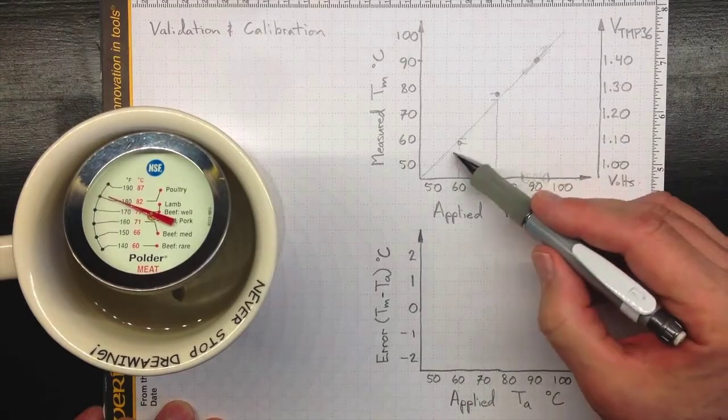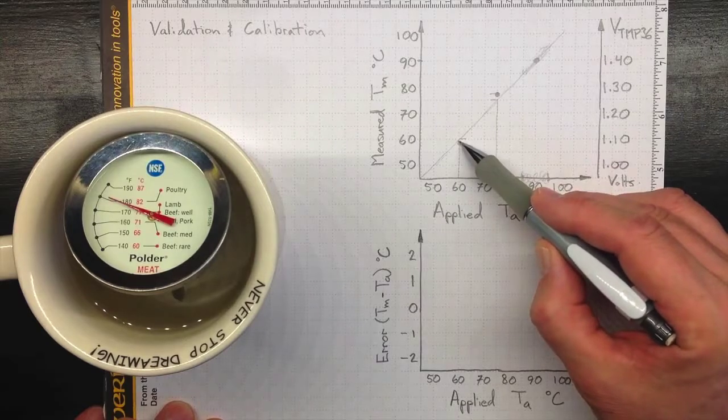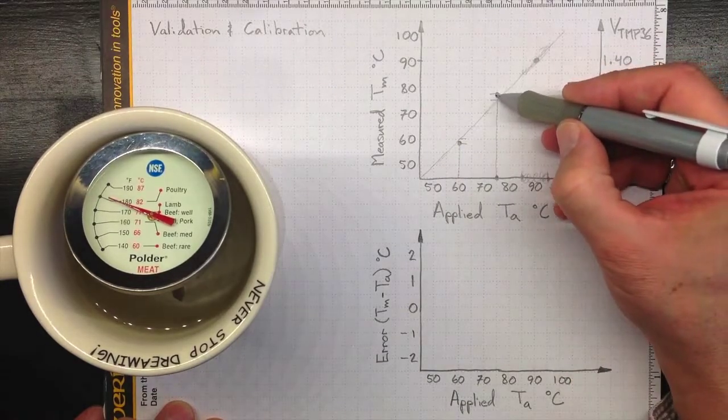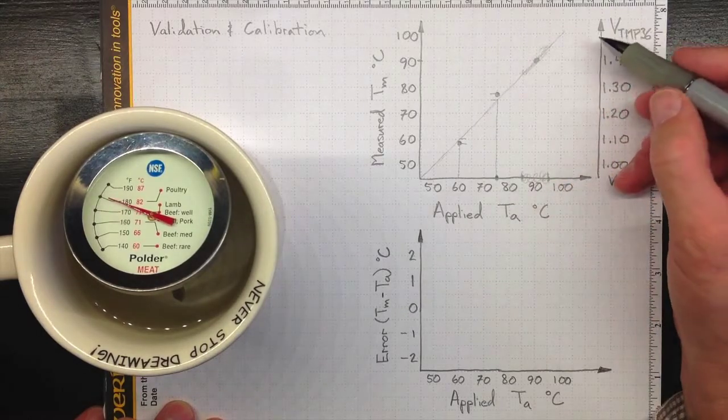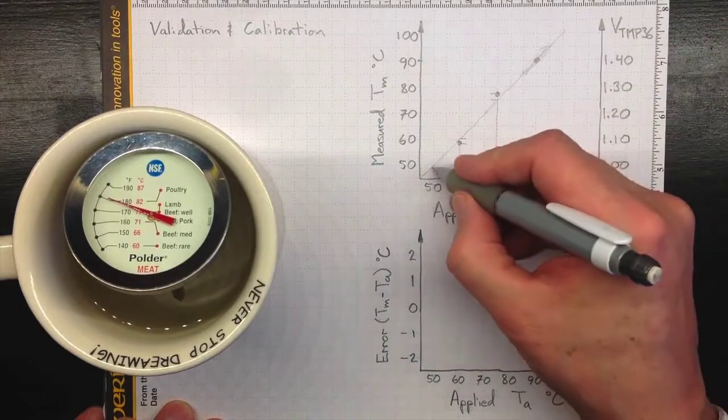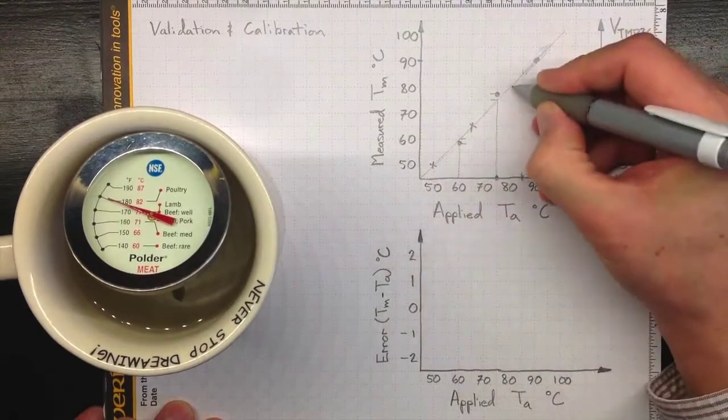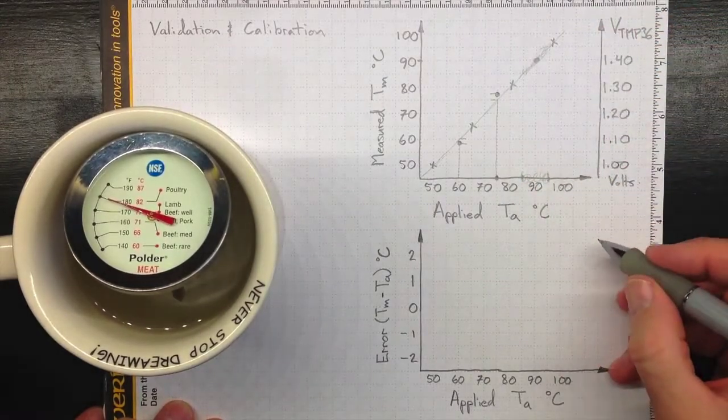Now, in most cases, if your instrumentation is any good, you won't really see these errors when you draw a graph like that. That would be an error of, say, 2.5 degrees Celsius. That's a pretty big error in your measurement system. So, more likely, your calibration relation will look something like this when you actually do the tests.